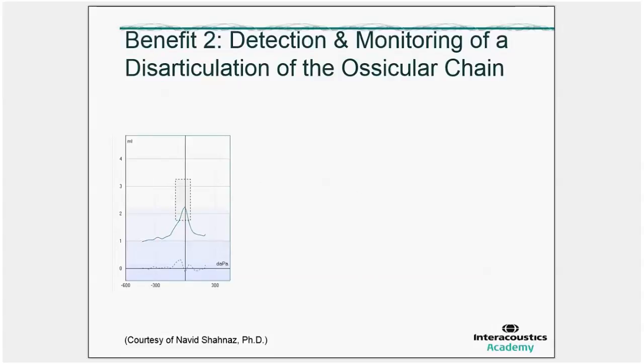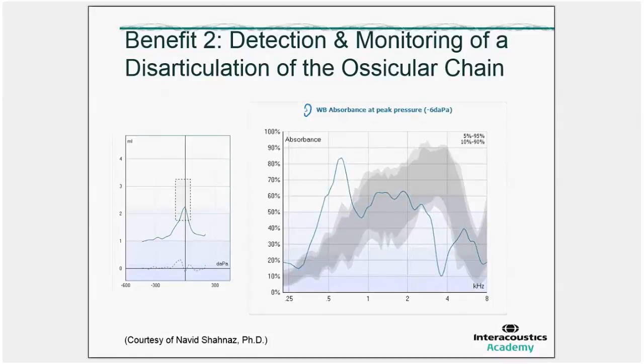Benefit number two. The detection and monitoring of a disarticulation of the ossicular chain. When using traditional tympanometry, then we expect a peaky tympanogram, but we cannot differentiate between a flaccid eardrum or a disarticulation of the ossicular chain. Now, with absorbance we can. This is a very nice example where we see that there is a high peak in the lower frequencies. There is also a very low peak between 3,000 and 4,000 Hz. But we don't look at that one. The relevance is in the very high peak close to the resonance frequency in the lower frequencies. This is a typical pattern for a disarticulation.